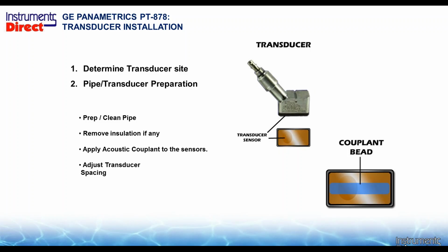What flavor of couplant depends on your application. The PT878 comes standardly with a bottle of, let's say, liquid goop. And the goop there is great for applications that aren't too hot, aren't too wet, and I'm just going to spot check. If I'm going to leave this there for a day, week, or month, then the liquid goop will run out. In that case, we need to use some silicone goop. And the silicone goop is just a little thicker gooey that ain't going any place under moist conditions. It's not going any place under warm, hot conditions. So you can use different couplants based upon the certain applications. If you're going to spot check, the liquid goop is just fine. If you've got a higher temperature, wet application, we have all different flavors of goop that you can use for your particular application.